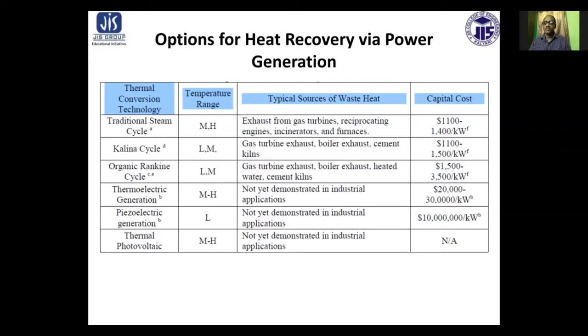Now the very popular method is generating power via mechanical work. First of all, mechanical work can be generated via waste heat through the steam Rankine cycle. The most frequently used system for power generation from waste heat involves using the heat to generate steam, which then drives a steam turbine. A schematic cycle is shown in the next slide. The traditional steam Rankine cycle is the most efficient option for waste heat recovery from exhaust streams with temperature above about 340 to 370 degrees centigrade.